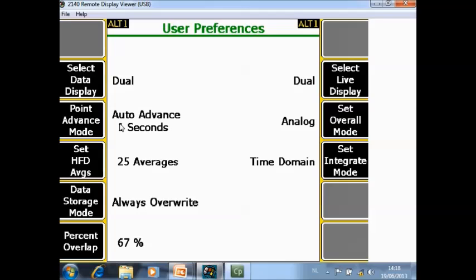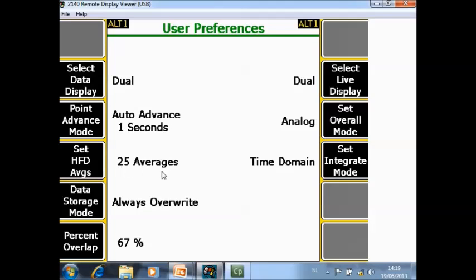F4 set HFD average. This is the number of high frequency domain averages, specified here to 25 averages. Typically for high frequency energy users want a high number of averages. Because it's high energy, data collection goes very fast and 25 averages is collected very quickly.